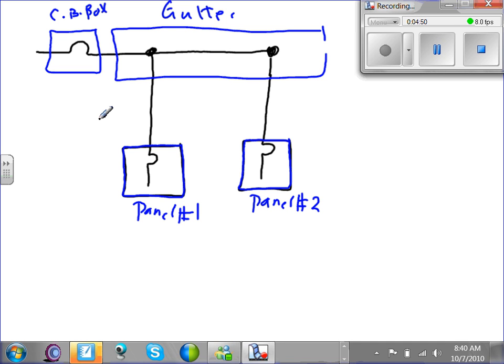Now what does a tap mean? When they say a tap conductor, anybody knows what a tap conductor means? What is a tap conductor? Is this conductor from the circuit breaker here all the way to the panels a tap conductor? No. A tapped conductor, guys, is a conductor that does not have an overcurrent device at the point of receiving power. For example, here's a point, this conductor here. Where did this conductor receive its power? Right at this point here, right? Does it have an overcurrent device right at the point of receiving power? No, then it's a tapped conductor.